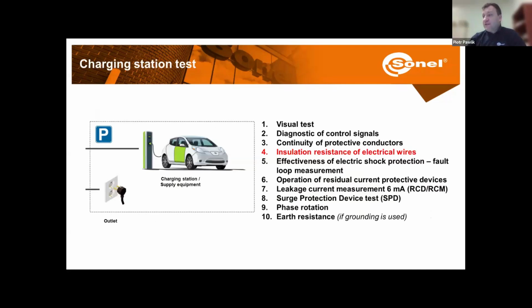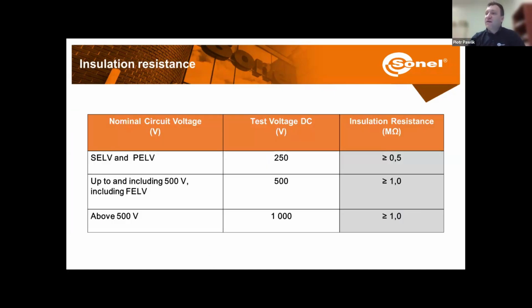Okay, next test, this is the insulation resistance. Here we have a table giving us what should be the test voltage and what's the requirement for insulation resistance, depending on the nominal voltage of the circuit. In most of the charging stations, we are going to have this situation, so up to 500 volts, and we are going to test this with the 500 volts DC test voltage, and the insulation resistance should be above 1 mega ohm.